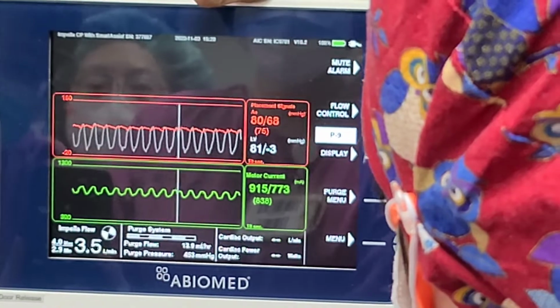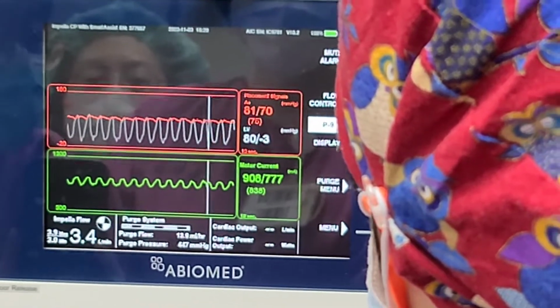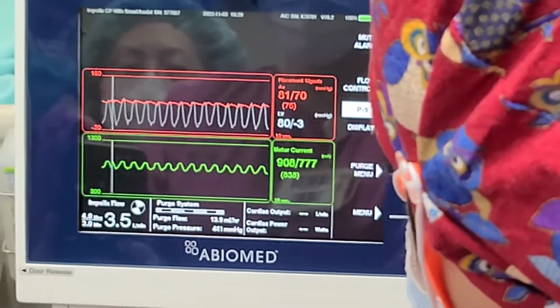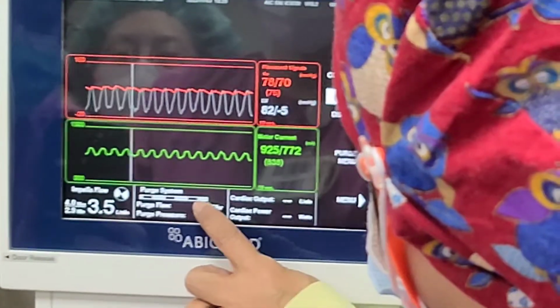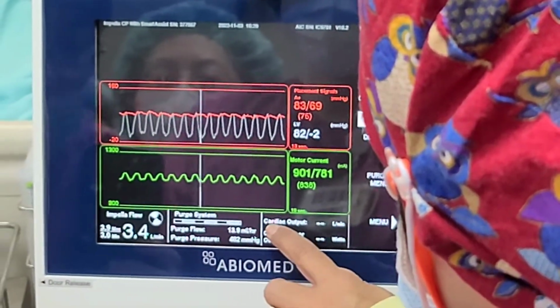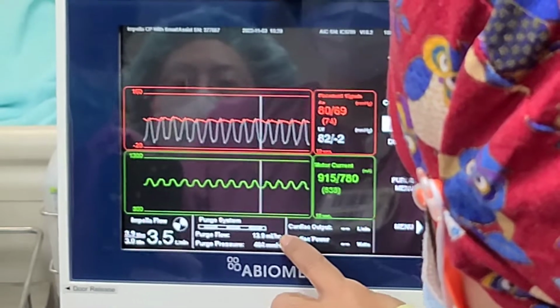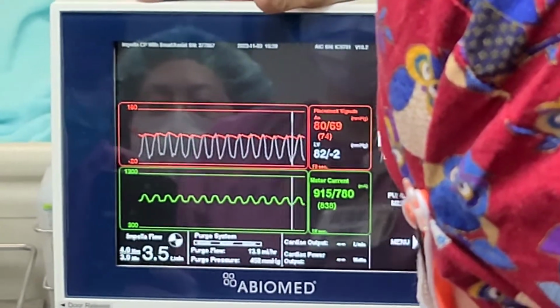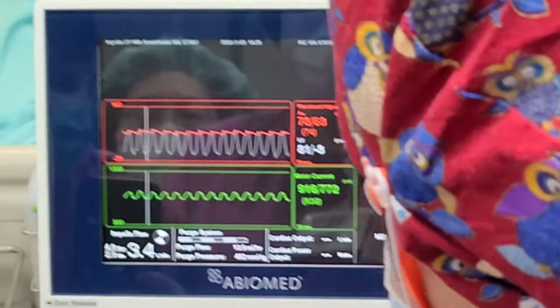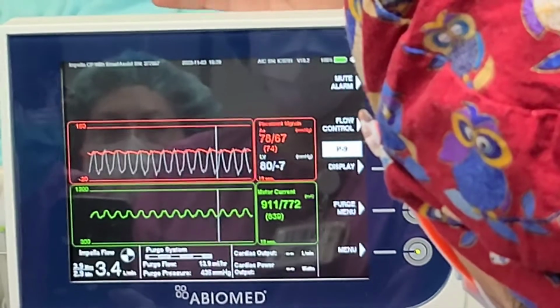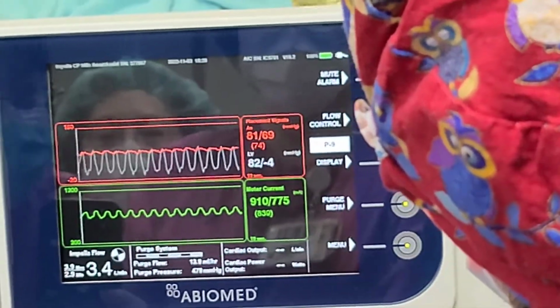Does anybody remember what your purge solution is? Dextrose 5 with heparin. So that is here - it will tell you the purge flow and the purge pressure. You cannot change this, this will be automatically done by the machine. So you don't need to worry how much do I give, what do I give - it's all done for you.